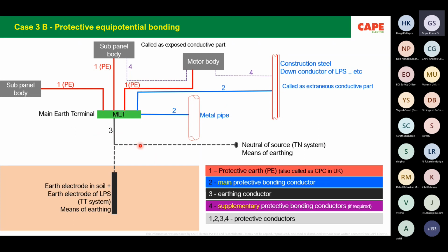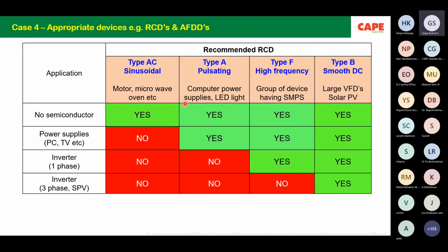You can think how many buildings in India include this protective measure. IS 3043, since 1965, has explained this measure very clearly in the standard. Unfortunately, if you look at the design of an electrical installation, or through the tender documents, you can always see that earthing is made as per IS 3043. IS 3043 is talking about equipotential bonding. It has given one picture of an earth pit in soil. If you read the content, you can be clear that the purpose of that picture is that if you require an earth pit, you make it in that fashion. So it's not a mandatory thing. What is mandatory is this protective equipotential bonding.